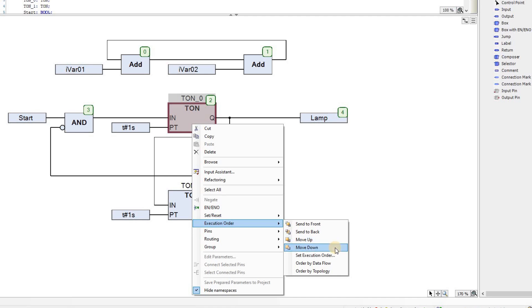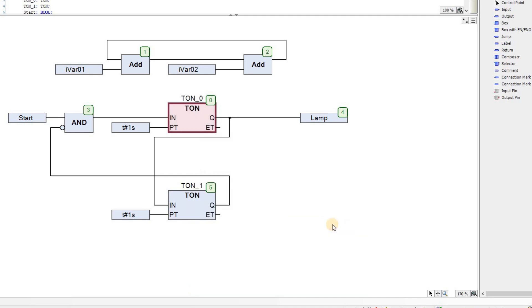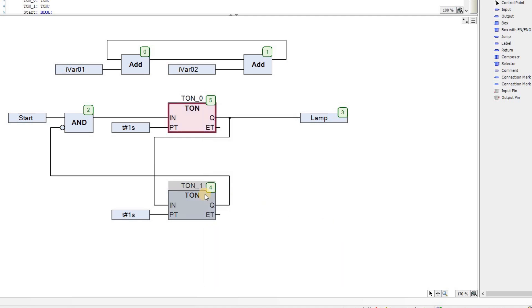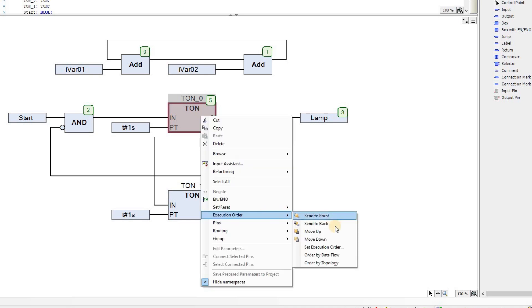If I choose Send to Front, Send to Back, Move Up and Move Down, and then Set Execution Order. If I choose Send to Front, the execution order of this block will be set to 0, meaning that it will be the first block in the POU to be evaluated. Then, if I choose Send to Back, its execution order will be set to the highest number, which is 5 here. And it means that this will be the last block to be evaluated in the POU.